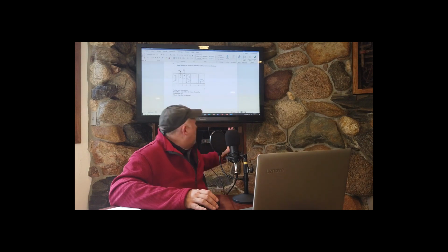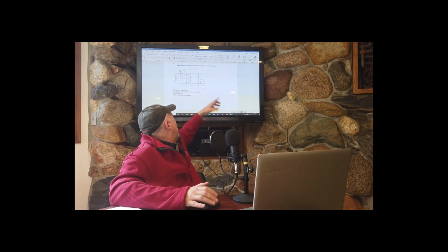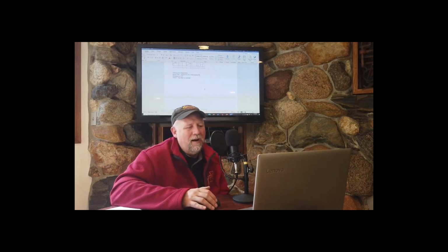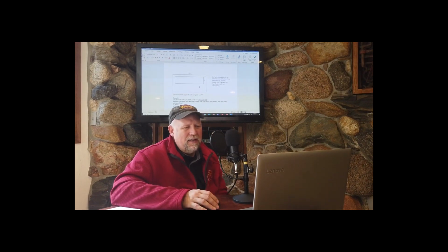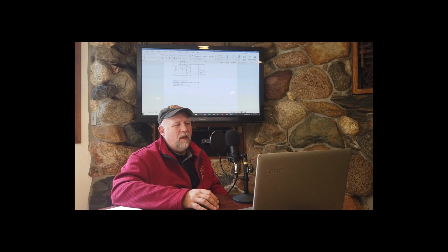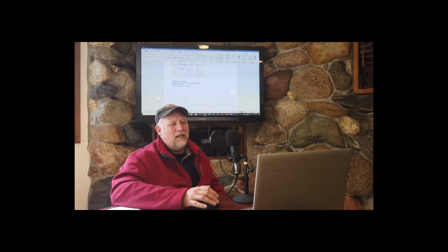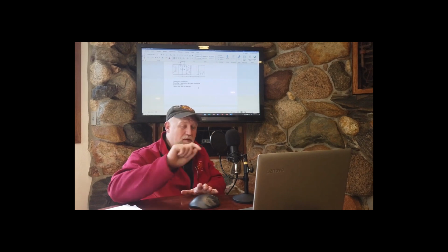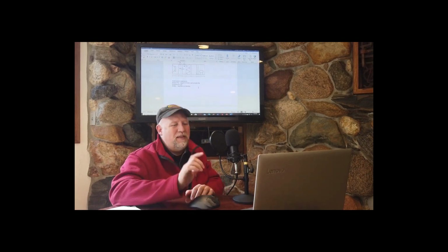All right, so now, once you've got all of those filled out, we can get the overall length for that air handler. And I want to say in the example that I did, if we've done this right, it ends up being 30 some odd feet long. That is a really long section of air handler. I want you to do it though, right? So put all those in, add it up, and this is the process.